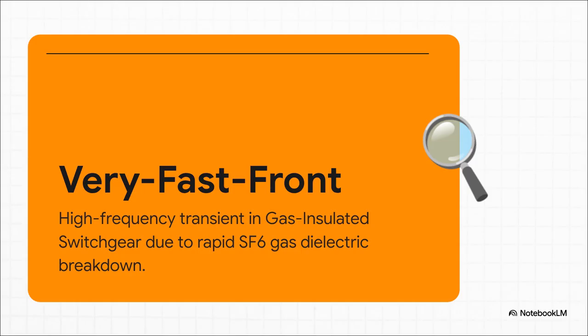VFTOs occur almost exclusively in gas-insulated switchgear, or GIS. They happen because of the incredibly rapid dielectric breakdown of the insulating SF6 gas during a switching event or a fault. We aren't even measuring in microseconds anymore. VFTOs operate on the nanosecond scale, pushing frequencies up to 50 megahertz.